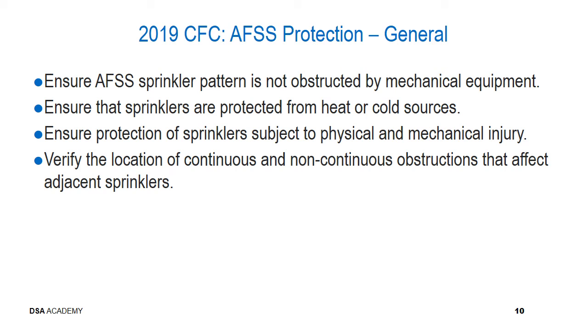NFPA 13, Section 3.3.18.1 notes that an obstruction located above or below the level of sprinkler deflectors that affect the discharge pattern of two or more adjacent sprinklers. 3.3.18.1 also notes that an obstruction located above or below the level of sprinkler deflectors that affects the discharge pattern of a single sprinkler. Therefore, it is important for the project inspector to verify both during installation and after installation that the sprinkler spray pattern is not impeded or obstructed.